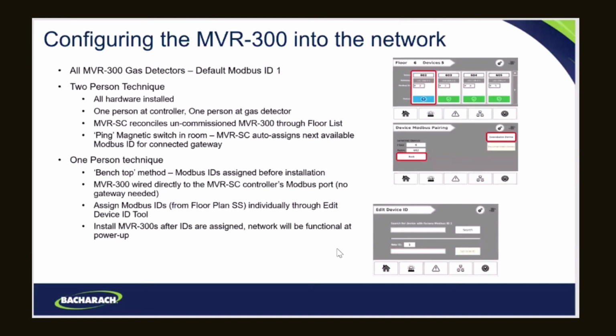Is there a preference of the two-person technique over the one-person technique? Seems like the two-person would be a little more effective or a little more efficient. Yeah, it's a little bit more efficient. It does require two people and maybe a two-way radio so they can talk to each other. Because the guy at the controller's got to pull up his side of it, and then the guy in the room's got to ping the gas detector with the magnetic wand. But after that, the system does everything else for you. You're just pressing buttons at that point.